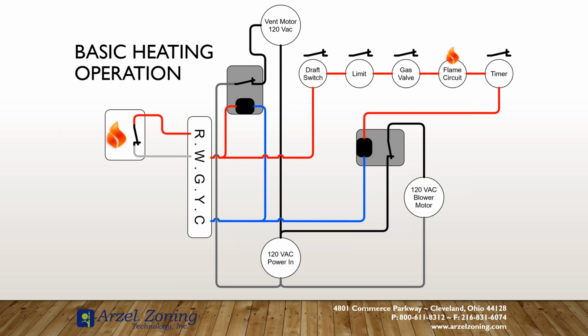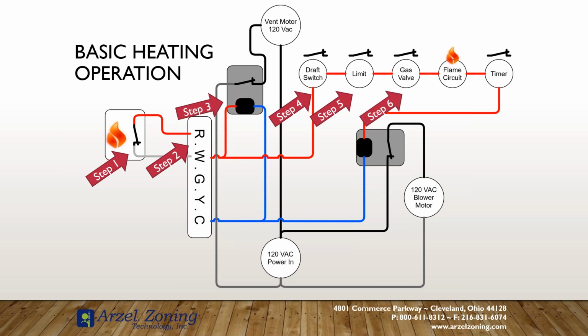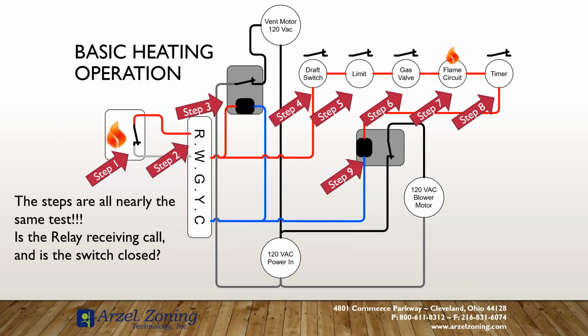So step one, we started our thermostat. From there, we prove it at our furnace. From our furnace, we make sure our vent motor starts, make sure our draft switch, our limit switch are closed. If those are closed, our gas valve will start. If our gas valve is proven to flame circuit, it starts our timer, and then our blower starts, and we have heat. And the steps are pretty much identical from one furnace to the next. It's just different configurations. So while it may look different because the furnace is set up differently, things are in different locations, it all operates exactly the same.